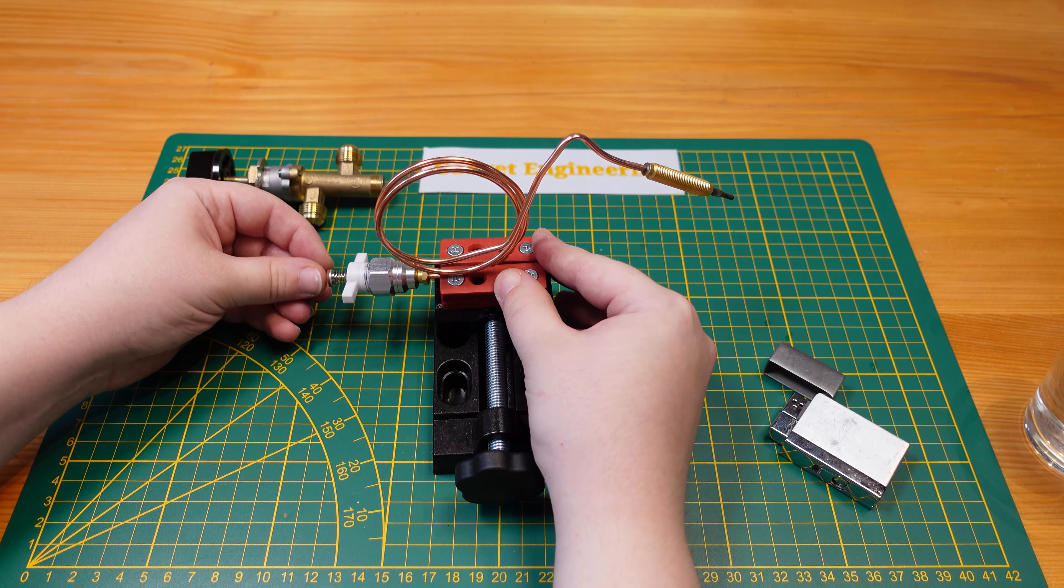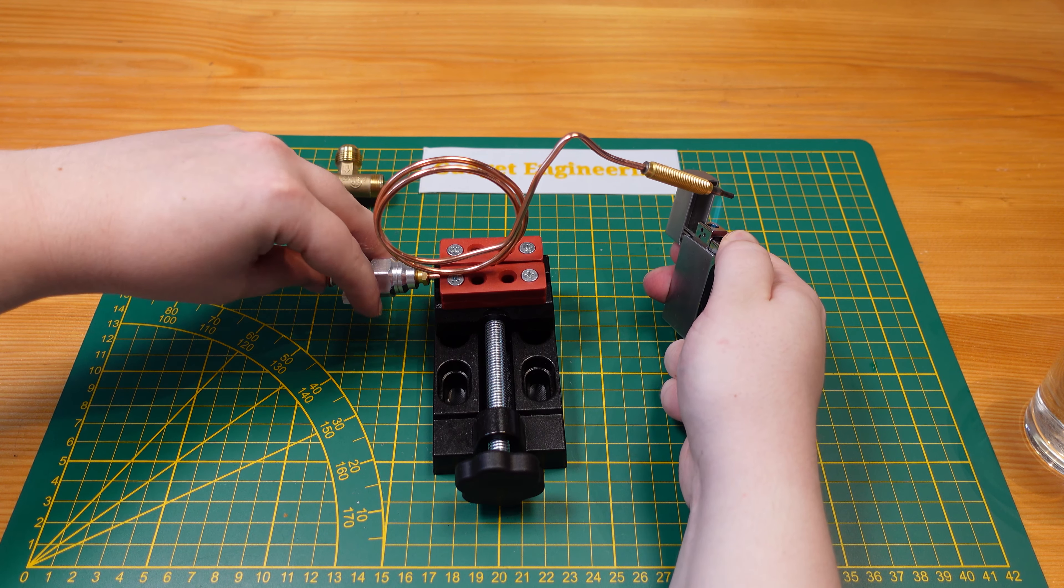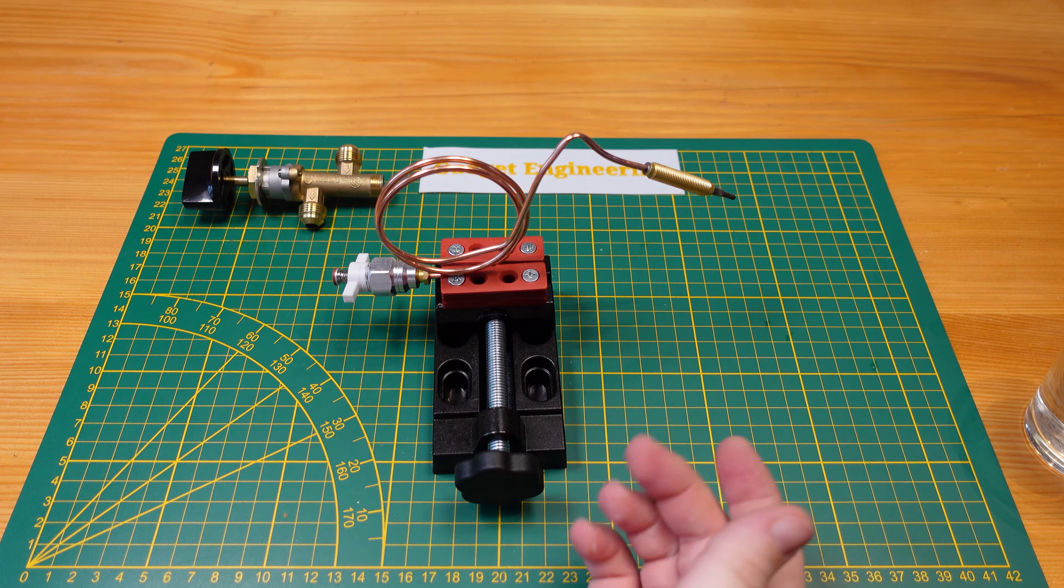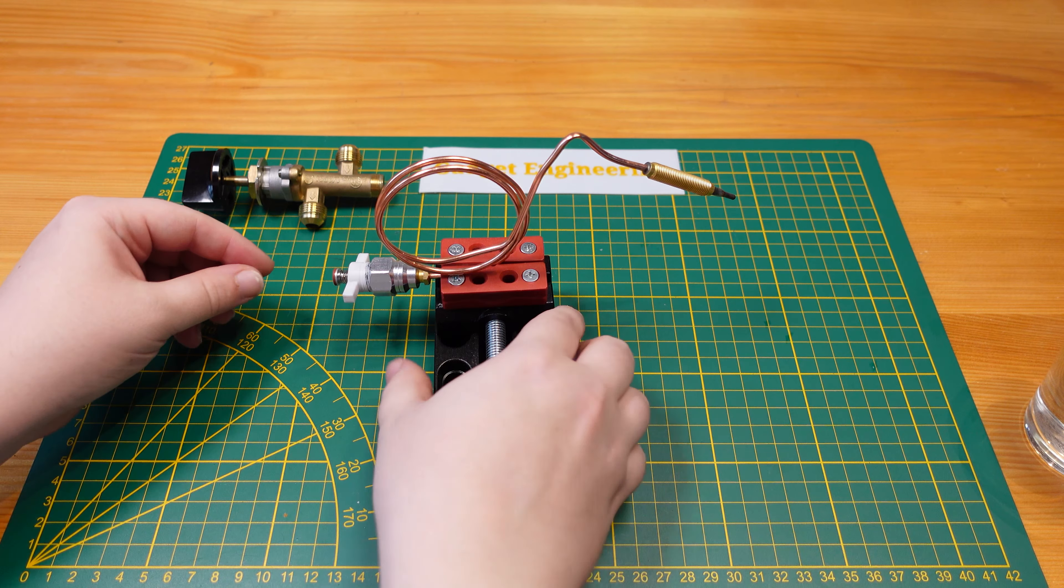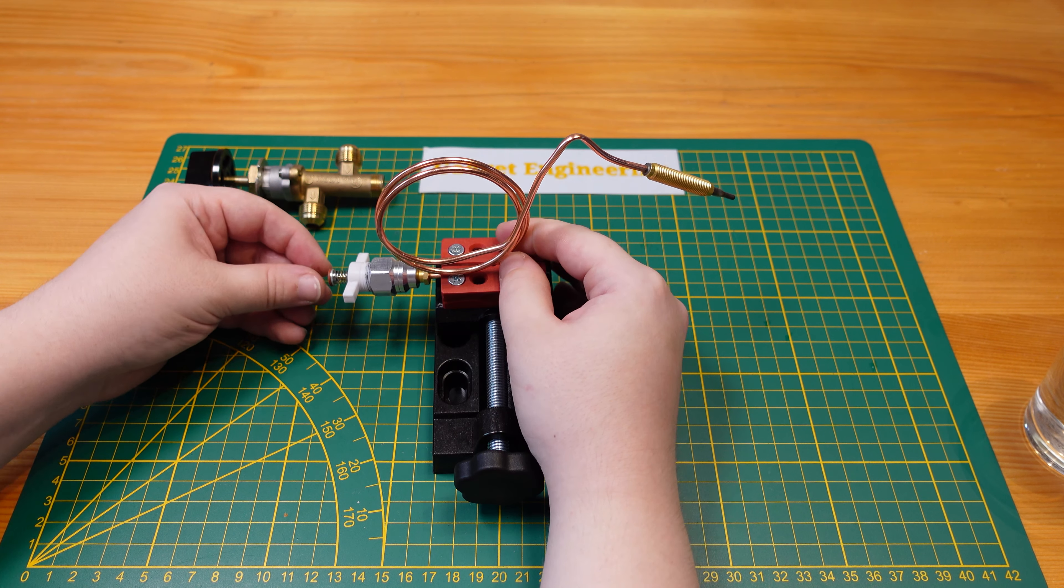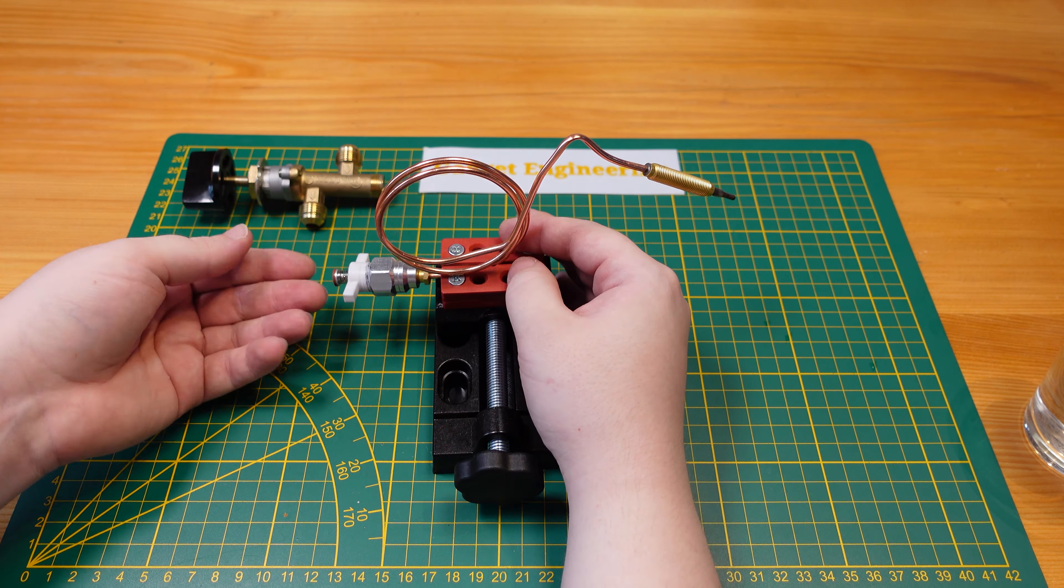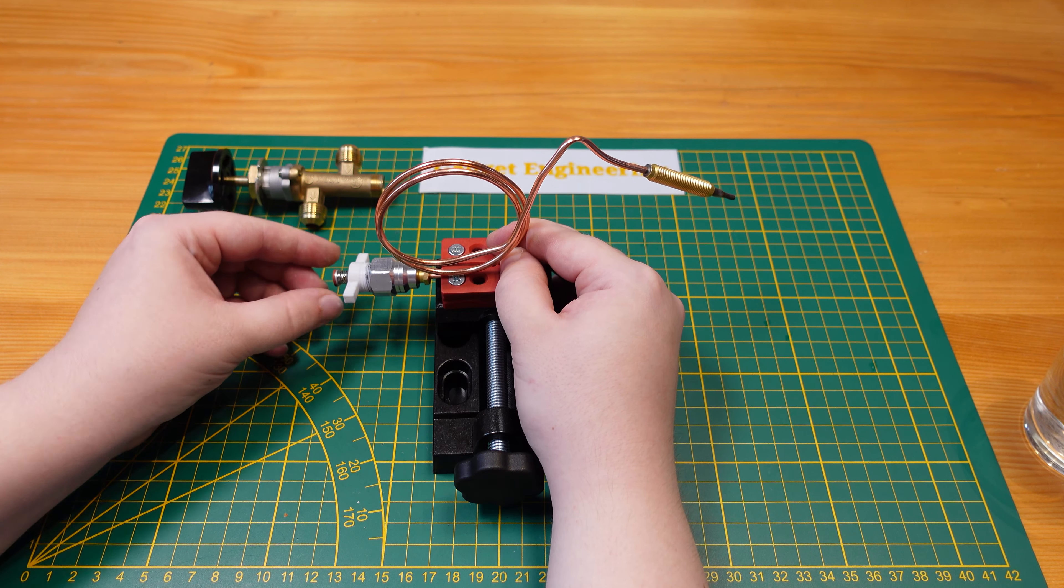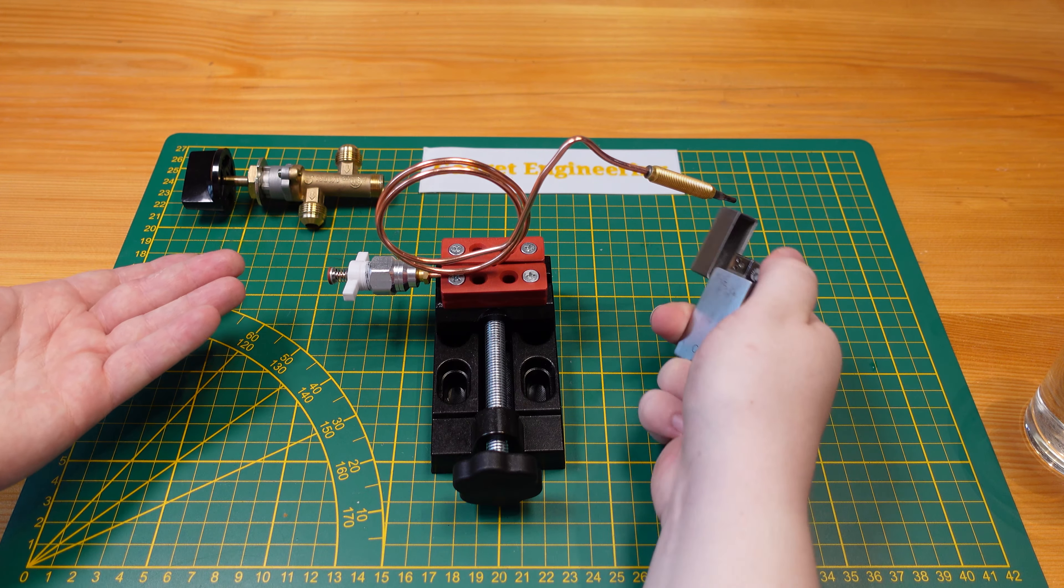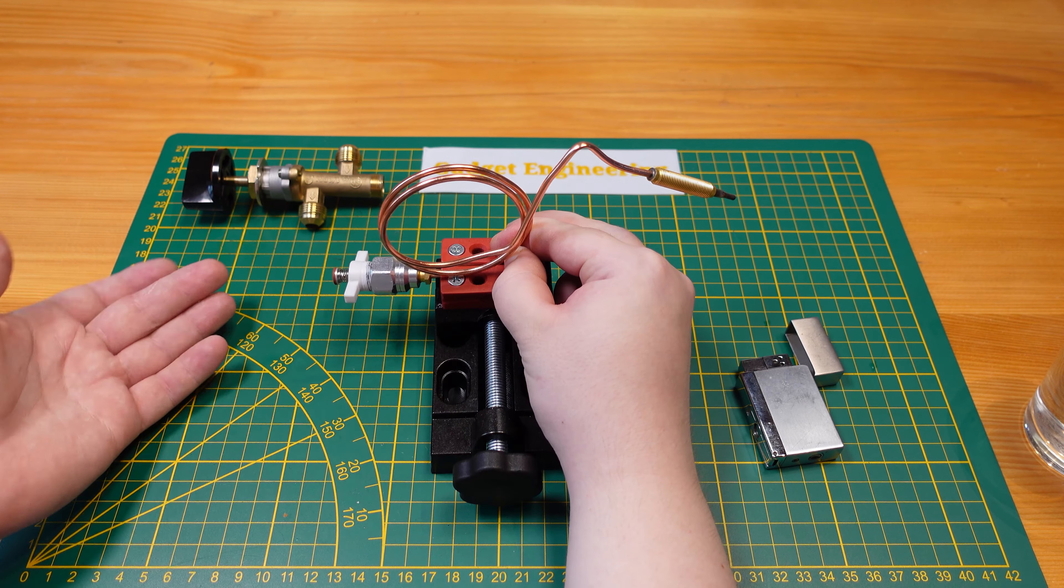So let's try it again. So now that it's cooled down, you can see it is closing under spring tension. If we heat it up again, you can see it takes a very little amount of heat actually, so I was just heating it under the gas flame for maybe five seconds. And already it is enough to maintain this spring tension. And you can see if I try and pull on this, I am able to release the spring, but it's still hot and generating this electrical current. So the spring again is being latched in if I pull on it. So I can feel it actually losing power. See now it is very loose and not generating enough current to hold it in. But already this amount of heating, as you can see, is enough to latch it.